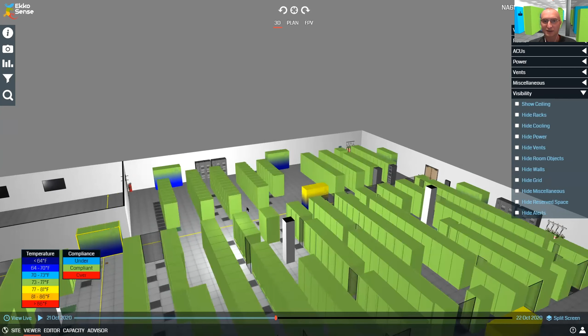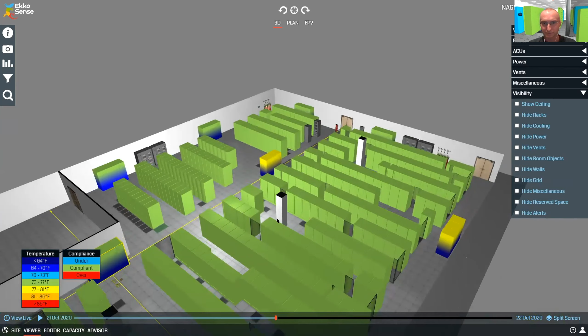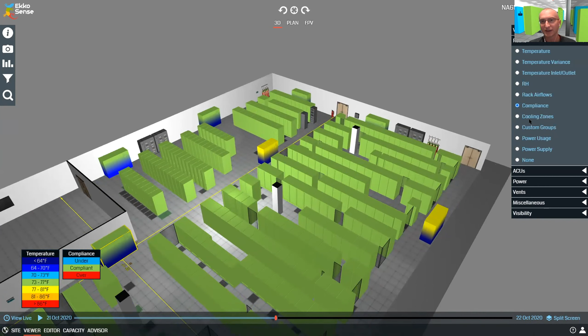If I turn this back to the temperature view, so it's a bit easier to see, and bring the racks back in, what we can also do with this view here, let's just spin it around a bit. We can use all the data that we're collecting from the rack temperatures and all the data that we're collecting from the air conditioning units. That combined together allows us to visualize cooling zones. So if I go back and see the last calculation it did for cooling zones, what this is doing is actually mapping the air conditioning units and how they're working with the racks that they are affecting.